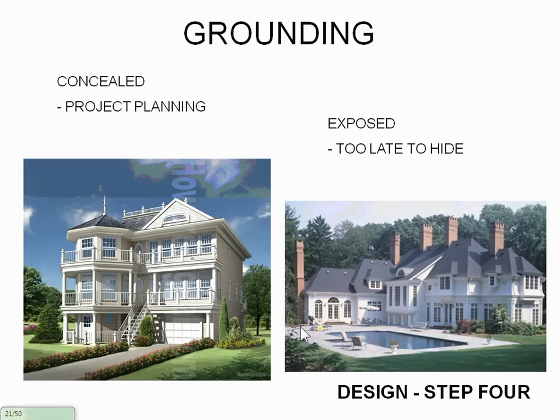The second thing would be you've got to ground your system. So what's the best way of doing it? Basically, if you have a brand new building, what we like to do is get the down leads concealed inside the building. The reason for that is you can hide it from the outside. It looks a little bit better. If your house is already up or your building's already up, we can route exposed on the outside of the building. But then again, will it work? Sure, but you'll see the cables all on the outside. So what we like to do is hide as much of this stuff as we can during the construction phase.